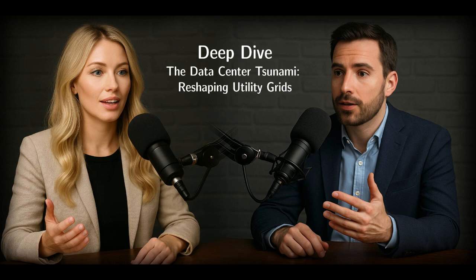Second, and this is critical, reliability requirements. Most big industrial customers might be okay with 99.9% reliability, which sounds pretty good. But data centers demand 99.99%, or even better, five nines sometimes. That extra 0.09% isn't just a number. For engineers, it's a total paradigm shift. It means going from 8.76 hours of acceptable downtime per year down to just 52.6 minutes.